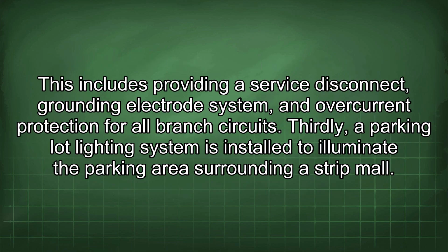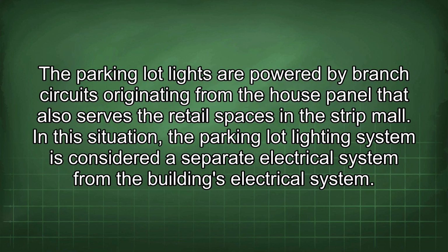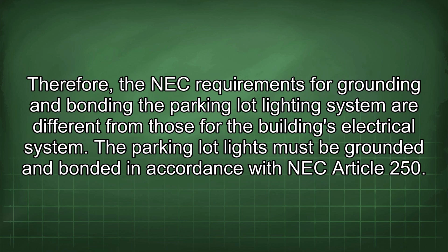This includes providing a service disconnect, grounding electrode system, and overcurrent protection for all branch circuits. Thirdly, a parking lot lighting system is installed to illuminate the parking area surrounding a strip mall. The parking lot lights are powered by branch circuits originating from the house panel that also serves the retail spaces in the strip mall. In this situation, the parking lot lighting system is considered a separate electrical system from the building's electrical system. Therefore, the NEC requirements for grounding and bonding the parking lot lighting system are different from those for the building's electrical system.